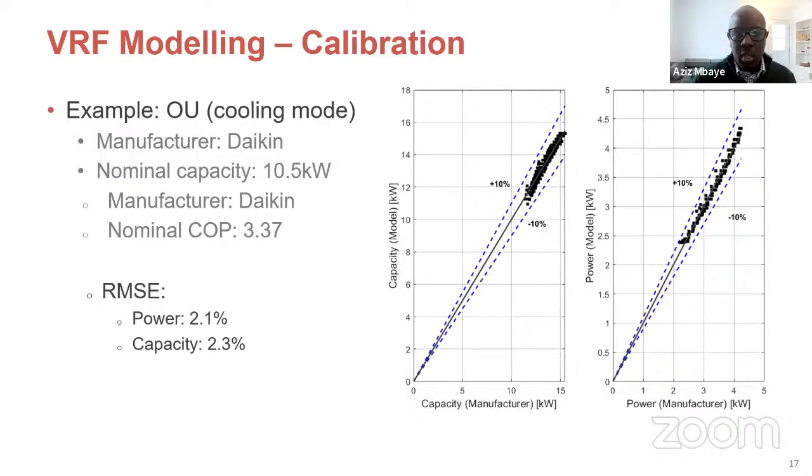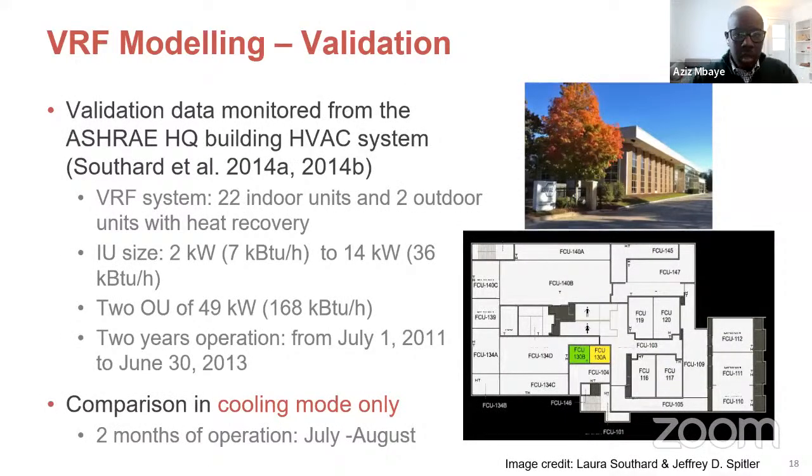So the last part will be to try to validate the VRF model using existing data from a system, and to do so, we simulated the calibrated VRF model, and the results are compared against data that are monitored from the HVAC system at the ASHRAE headquarters building located in Atlanta, Georgia. The data were recorded from a VRF system of 22 indoor units that served the zones of the building first floor.